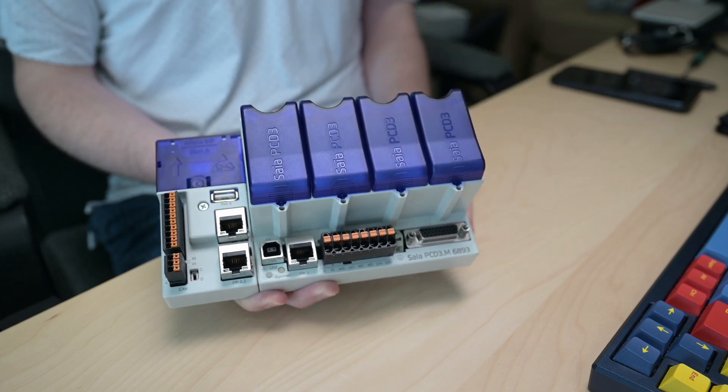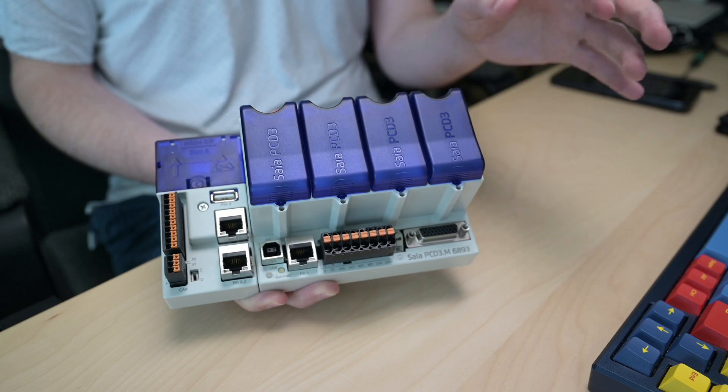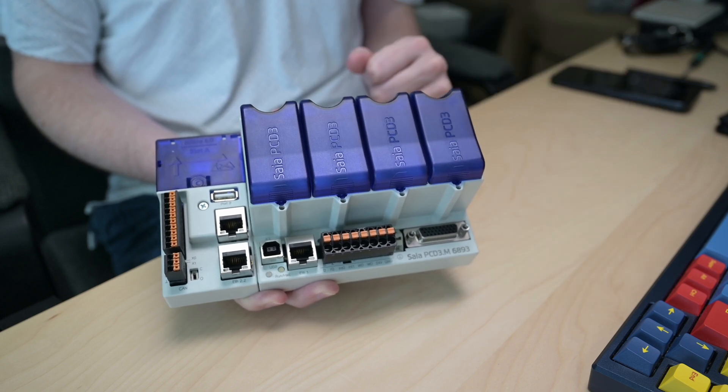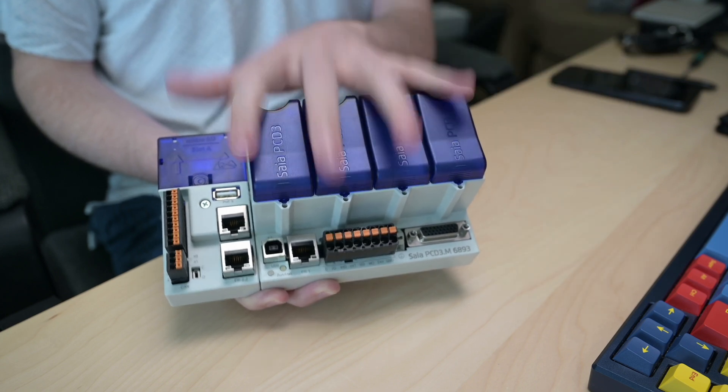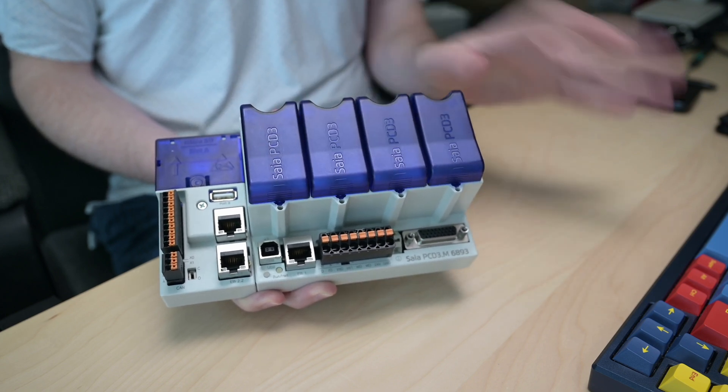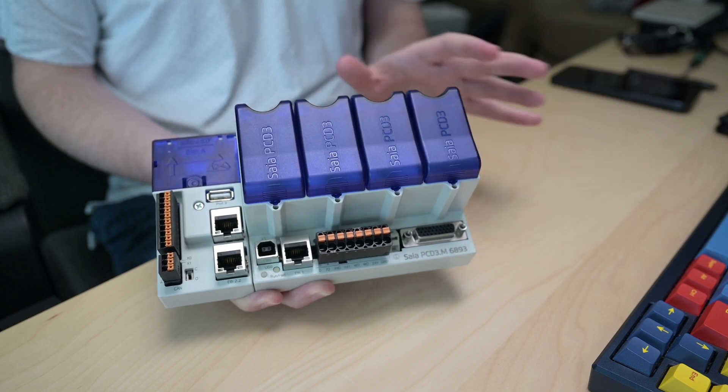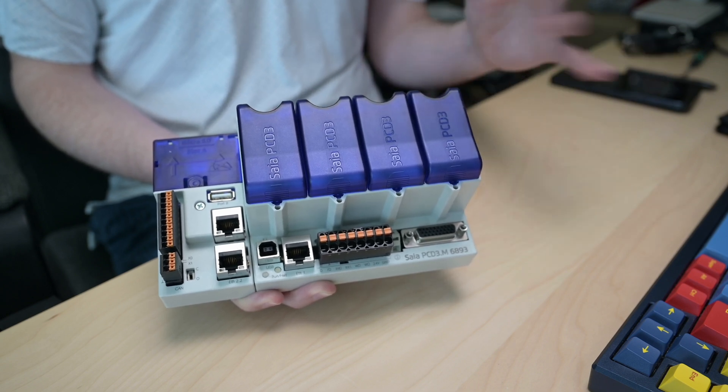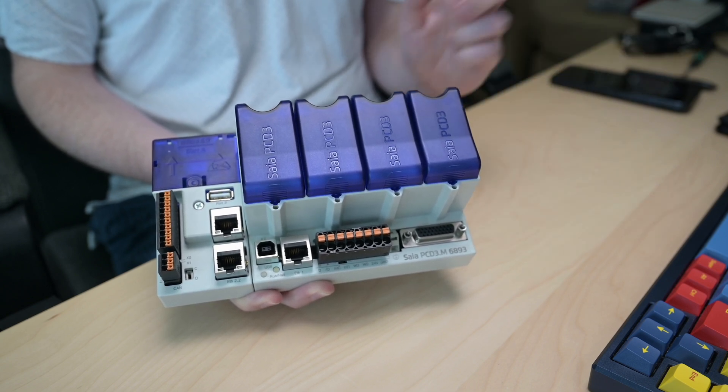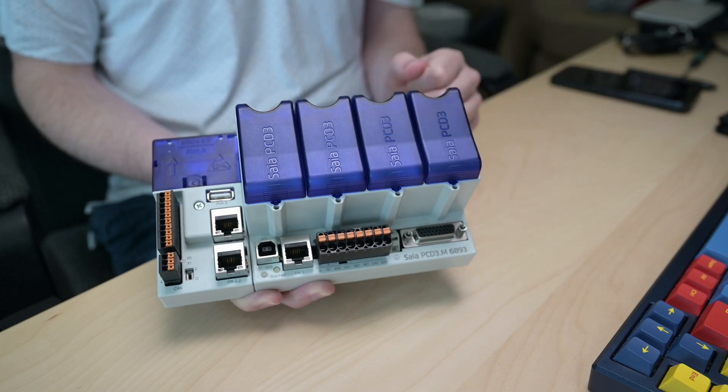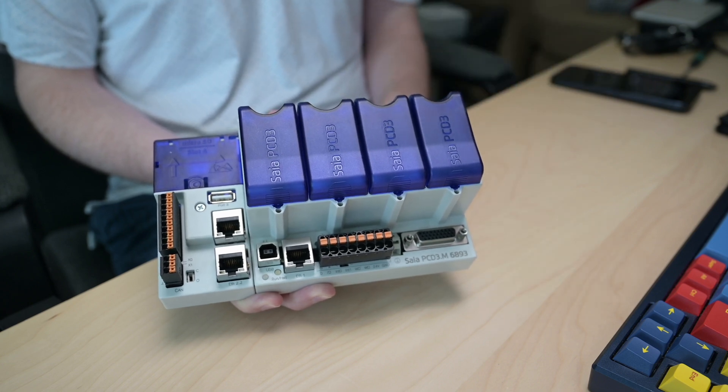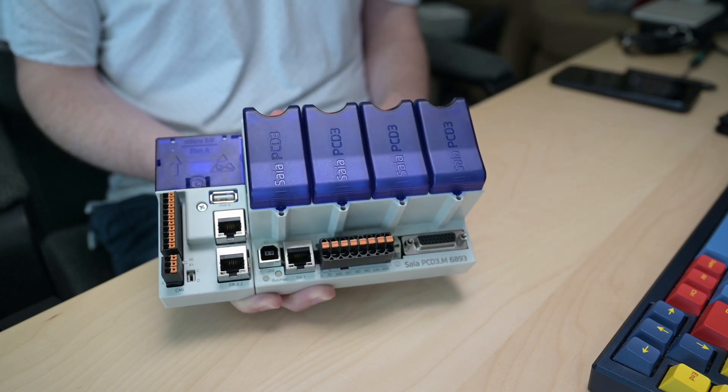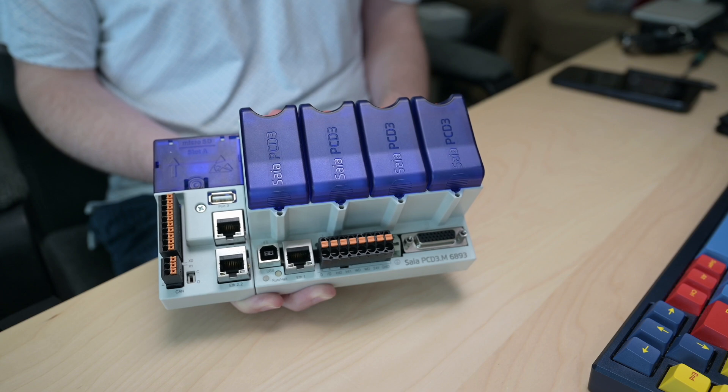Controllers themselves would determine who's the primary, secondary, while they're talking directly to one another. If one fell out, they would be synced up. They would have the exact same status and point values across the two of them. You would probably not even notice that the other one went down.